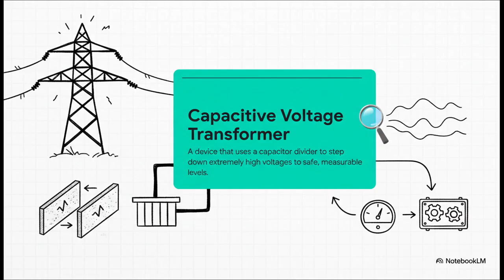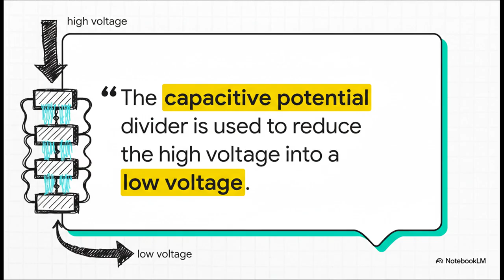Let's see how this device actually works its magic. The idea is to take that wild, high voltage and gently tame it into something we can work with. The main principle here is capacitive voltage division. The CVT uses a stack of capacitors connected in series. The super high voltage is fed in at the top, and as it travels down through each capacitor, it gets divided into a much smaller and more manageable value by the time it reaches the bottom.